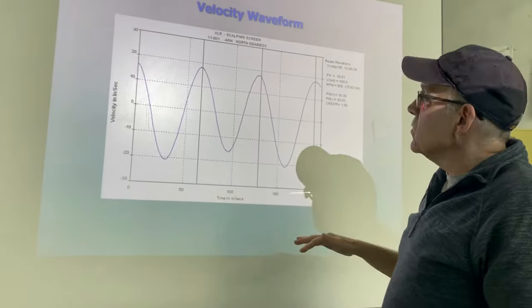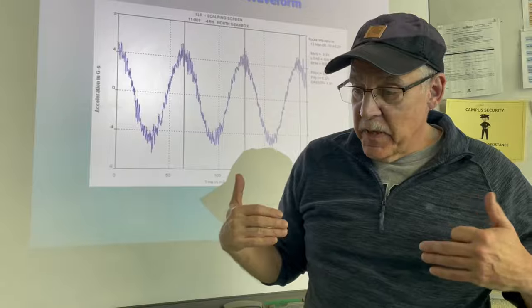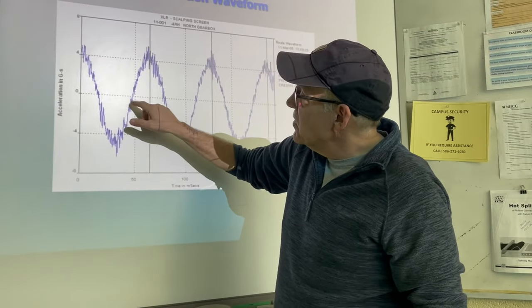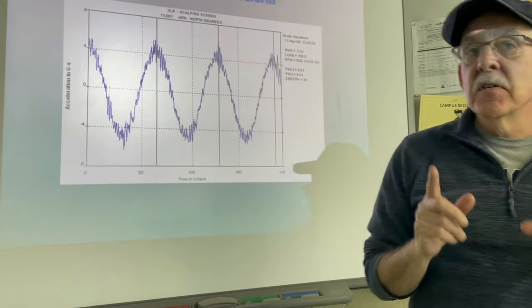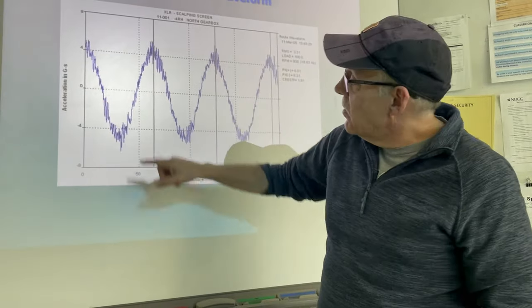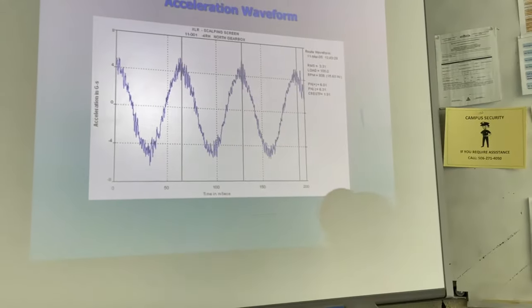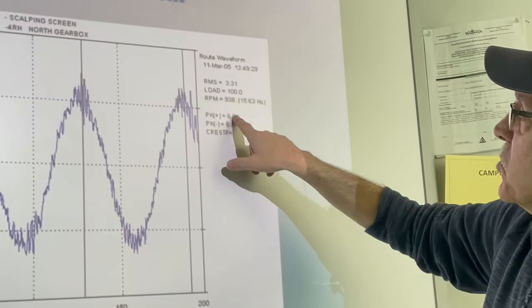When we switch to the next one, there's something else going on with this. Not only is that piece of equipment vibrating 16 inch seconds back and forth every revolution, but inside those revolutions we see all these spikes in acceleration, and remember, a bearing shows up in acceleration first, in the early warning of the bearing. So we're measuring acceleration now, and we see something else is happening. As that thing is shaking back and forth, there's another vibration in there too. What vibration, right?